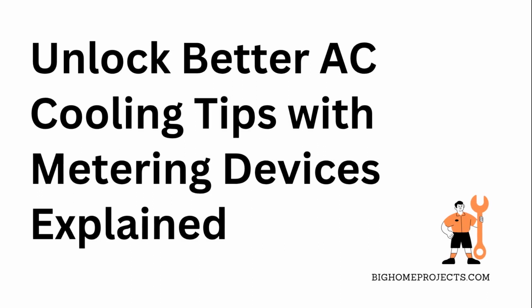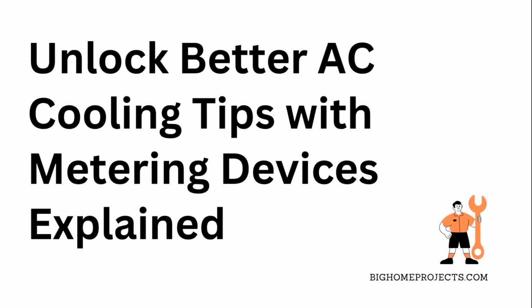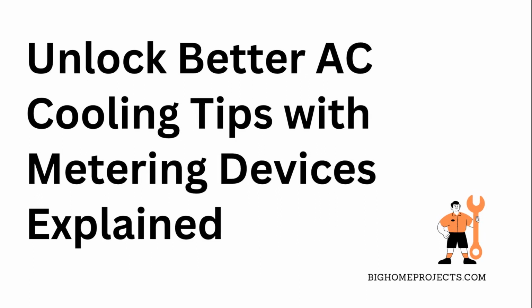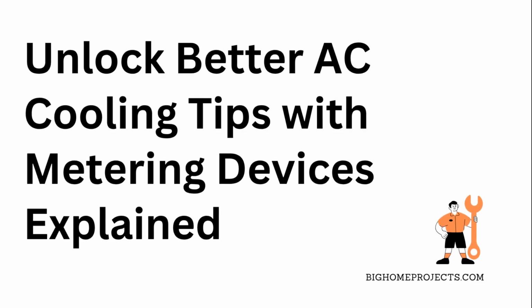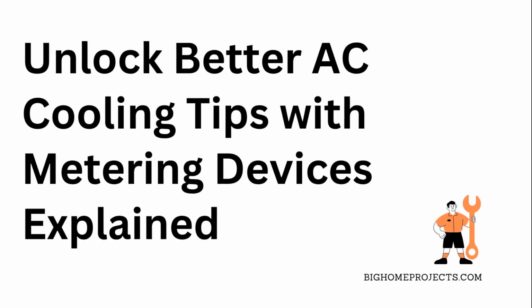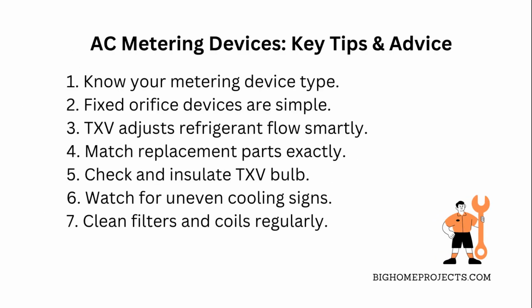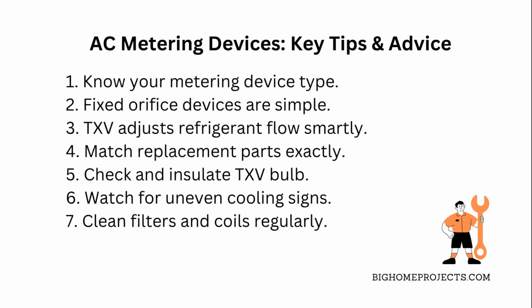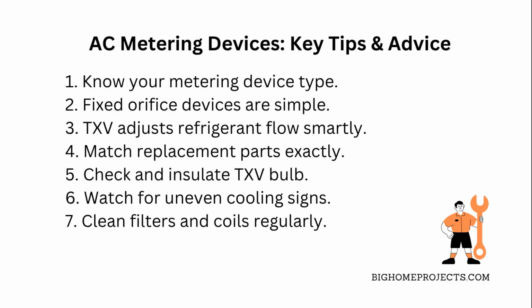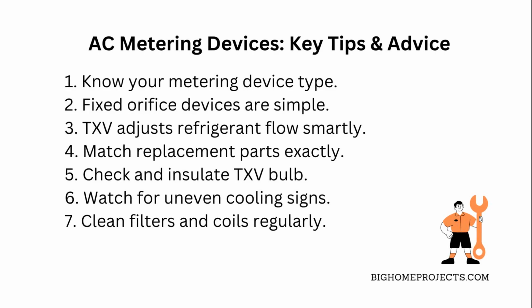Knowing your air conditioner parts, especially the types of metering devices like fixed orifice and thermostatic expansion valves, can totally change how you handle cooling issues. So first off, the fixed orifice devices like pistons and capillary tubes are pretty much simple devices that regulate refrigerant flow by size. No moving parts, just a set hole that lets the right amount through.